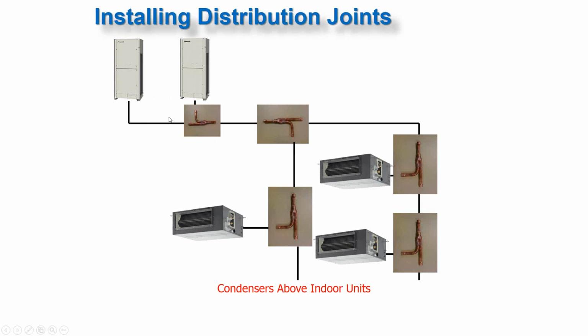So this is just one refrigerant line. For a heat pump system, we have two refrigerant lines. We have a liquid line and a suction line. The diagram just shows one of the two, but just imagine there's two, a liquid line and a suction line. So everywhere where there's a joint, there's going to be two joints. And you can see the connections here for liquid and suction line for our refrigerant piping.